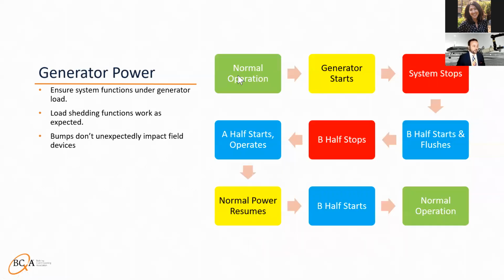There's generator power systems. We talked a little bit about this before. The steps that'll happen in some cases when the building goes into generator power: you'll be in normal operation, the generator starts and the baggage handling system stops. The B half, so half of the system, will start and flush all of the bags, and it'll stop. After that, the A half starts and can continue operating. It's often too expensive to size generators to run the entire building, so you might just go with half. Once normal power resumes, you'll want to make sure that the B half starts and enters normal operation.